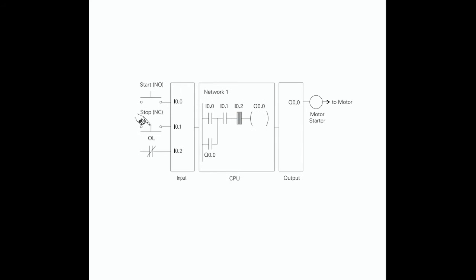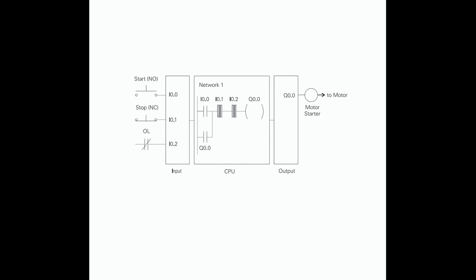The motor will continue to run until the stop push button is depressed. Input I0.1 will now be a logic 0, false. The CPU will send a binary 0 to output Q0.0 and the motor will turn off. When the stop push button is released, the I0.1 logic function will again be true and the program is ready for the next time the start push button is pressed.